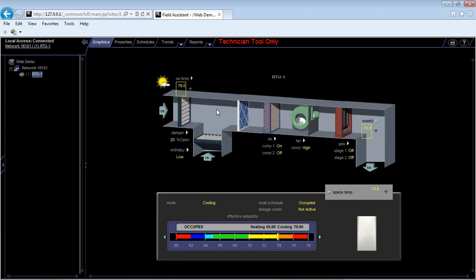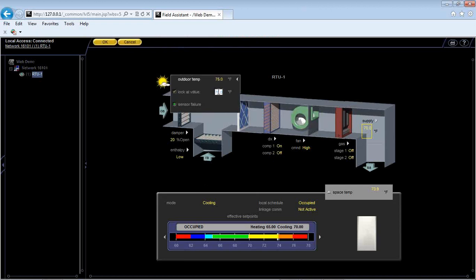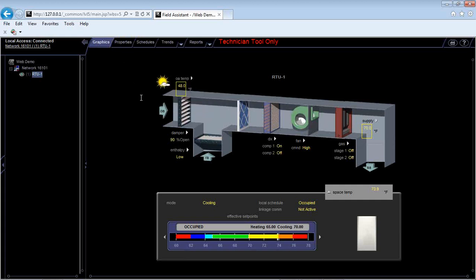Let's say that I wanted to try to use my economizer air. If I switch this value down to 48 degrees, hit OK, now I'm going to try to actually use economizer to cool my space. And you can see my economizer just fully opened. These controllers can do integrated economizer, so they can do economizing with compressors as long as the compressor is allowed to run on its outdoor lockout. But this is kind of the process that we would go through if we're testing one of these units, because obviously when you're commissioning one, your outdoor air is not always available to let you do heating and cooling, right?